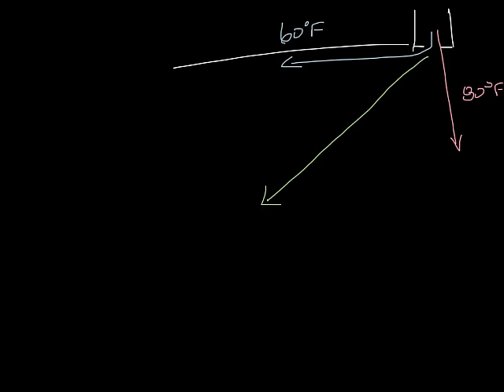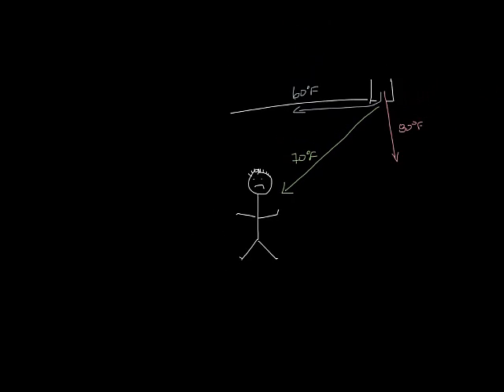So let's draw a perimeter again with our slot diffuser here. So at 60 degrees it may be in the fully cooling position, and at 80 degrees it might be in the full heating position, but as it moves between the two, it'll kind of sweep through the room. But when it has 70 degrees supply temperature, it could be directing it at a 45-degree angle into the space and directly at an occupant in the space. So let's move him up into the corner now.